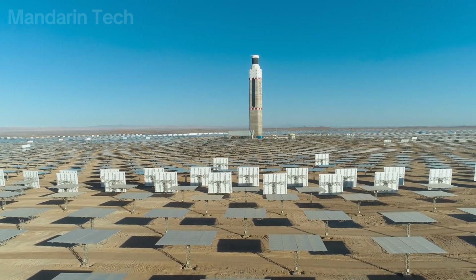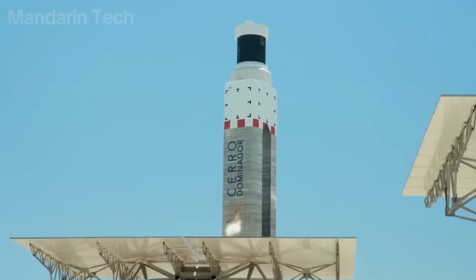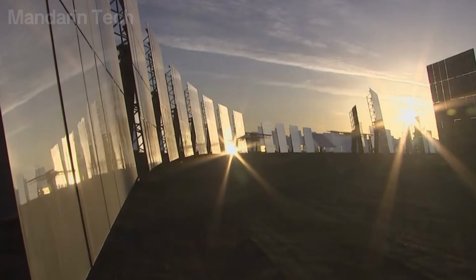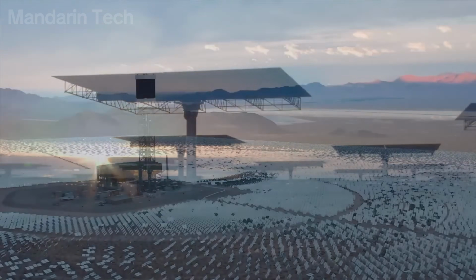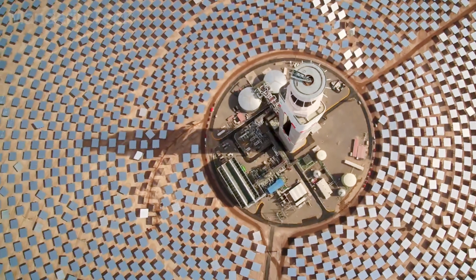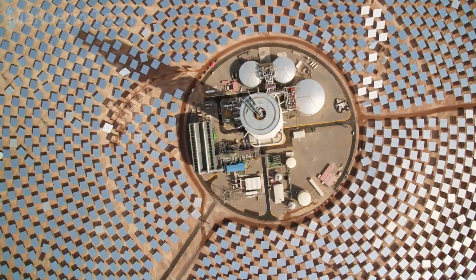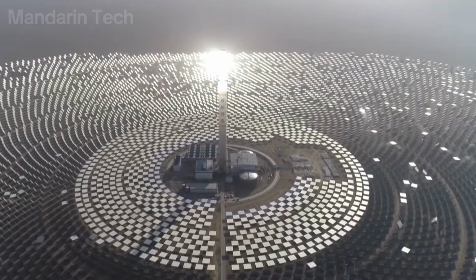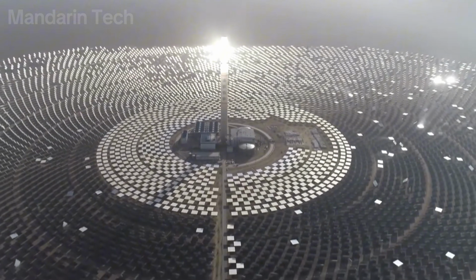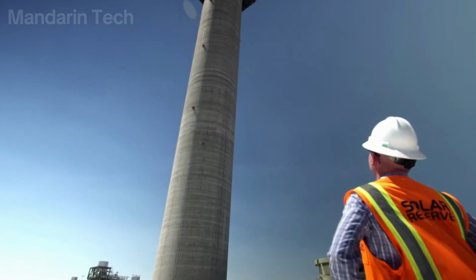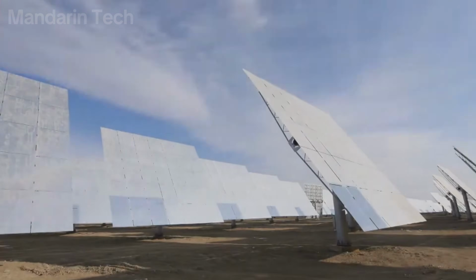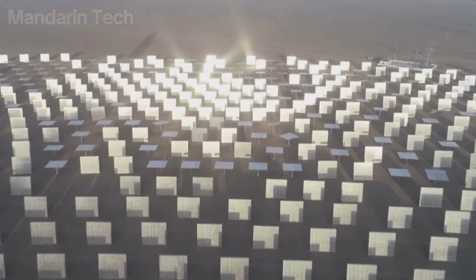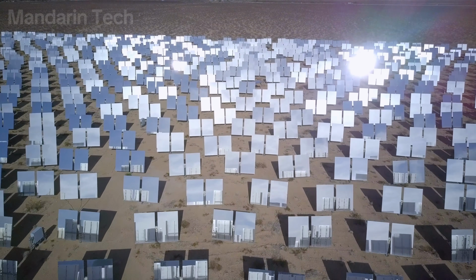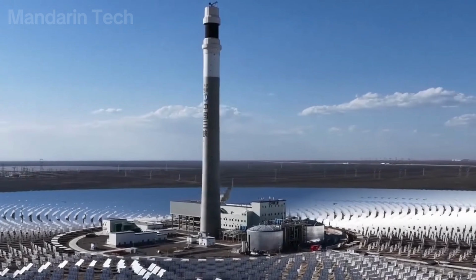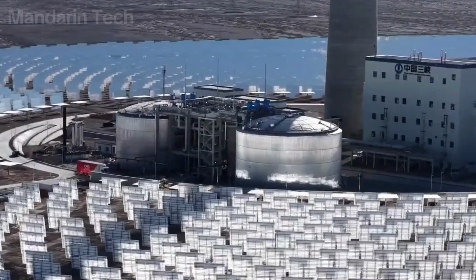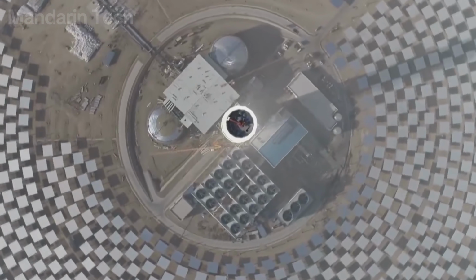Cerro Dominador introduces a different approach to solar energy, capturing sunlight during the day, storing it as heat, and releasing it according to the needs of the power grid. As a result, electricity generation is no longer strictly tied to the hours when the sun is shining. The project's greatest value lies in coordination. The high-rise structure must meet optical requirements, the heliostat field must maintain precise orientation, and the control system must simultaneously balance thousands of reflected beams. Below, molten salt continuously carries energy through a network of pipelines, valves, and heat exchange equipment.